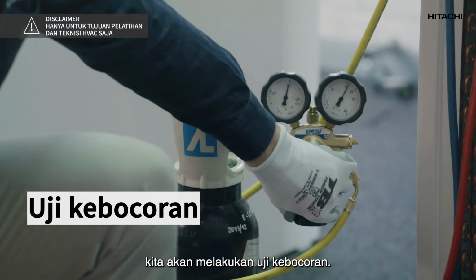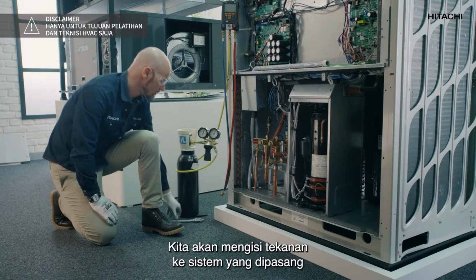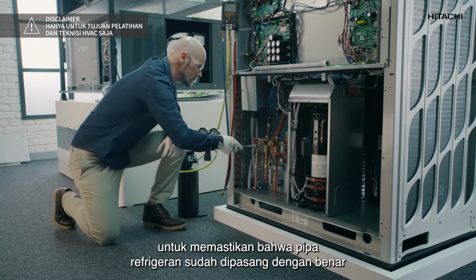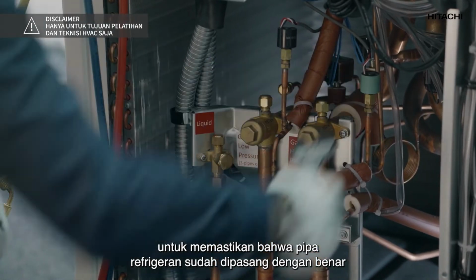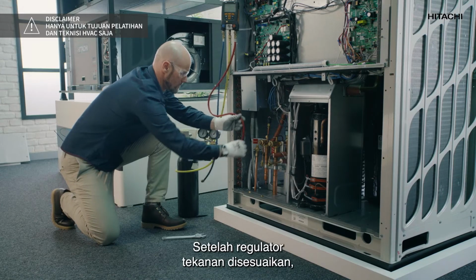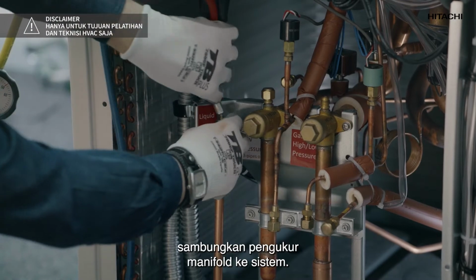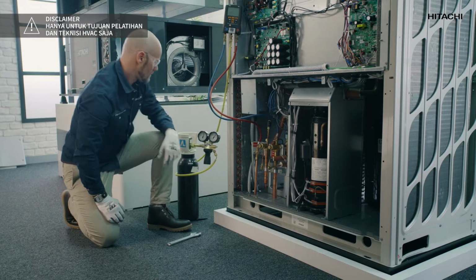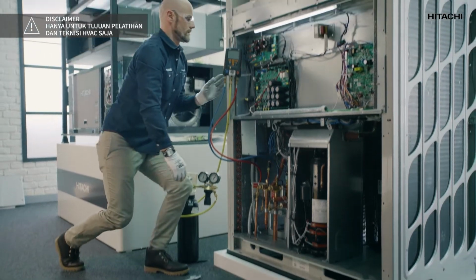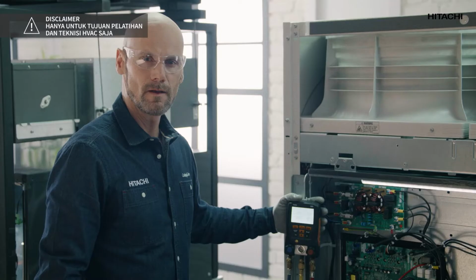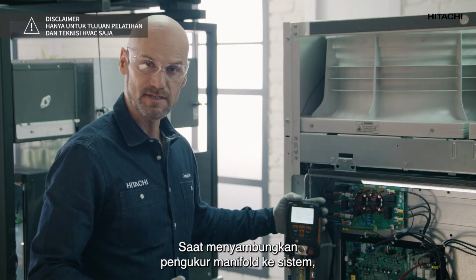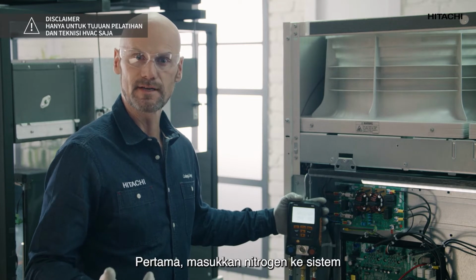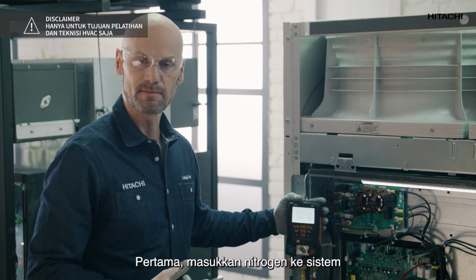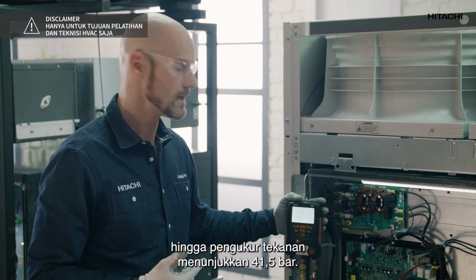Once the setting is finished, we're going to carry out the leak test. In other words, we're going to pressurize the installed system to make sure that the refrigerant piping is properly installed and that there are no leaks. Once the pressure regulator has been adjusted, connect the manifold gauge to the system. When you connect the manifold gauge to the system, you have to do the leak test. To do this, we introduce nitrogen into the system until the pressure gauge shows 41.5 bar.